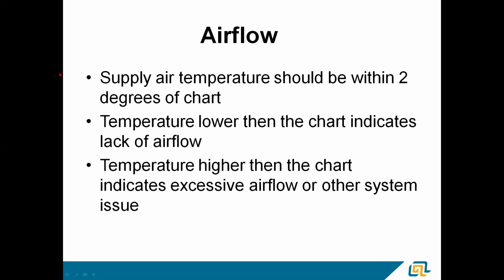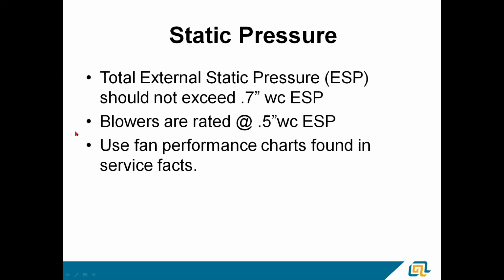Airflow: your supply air temperature should be within 2 degrees of that chart. You're never going to get spot on, but it should be pretty close. 2 degrees is definitely doable. A temperature lower than the chart indicates lack of airflow. You've got to get that blower moving a little bit faster. A temperature higher than the chart indicates too much airflow, too much load on the system, or something else, like you could have a TXV that's partially restricted or something like that. We're just not getting the proper amount of refrigerant into the coil. So just a couple of points to look at. Make sure it's got enough air and it's working well.